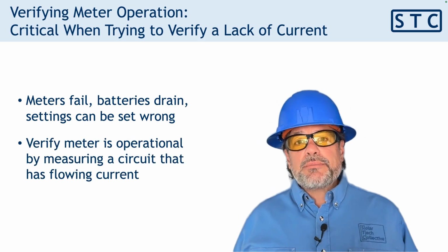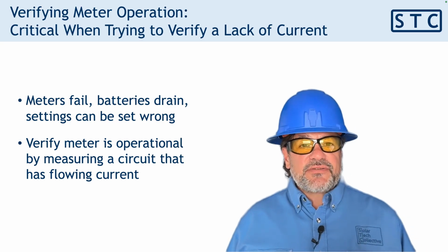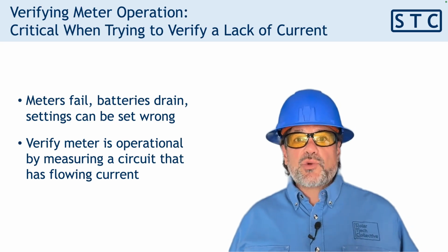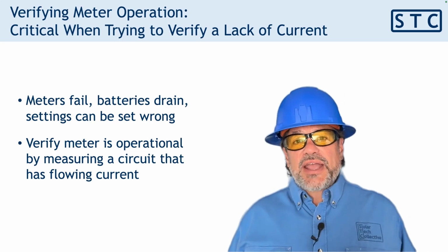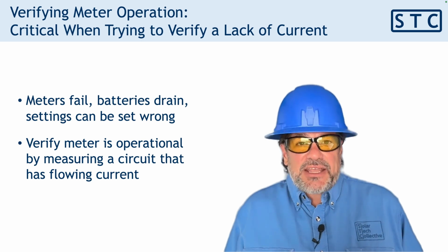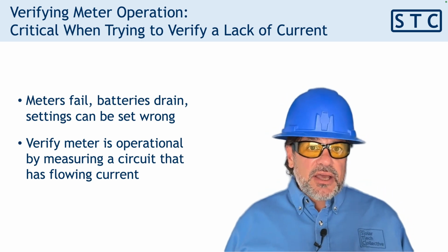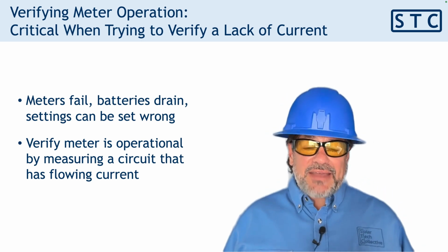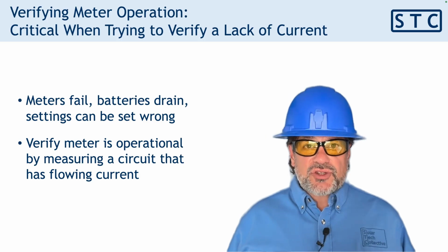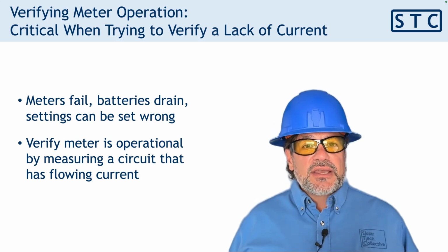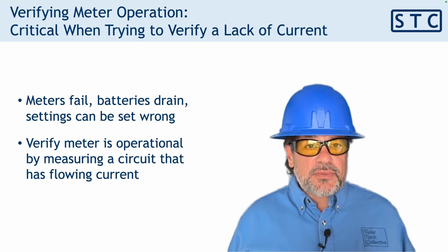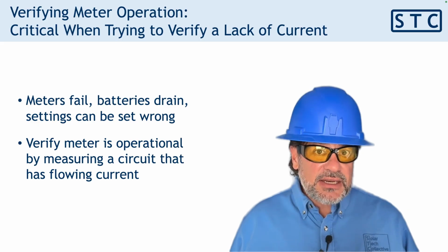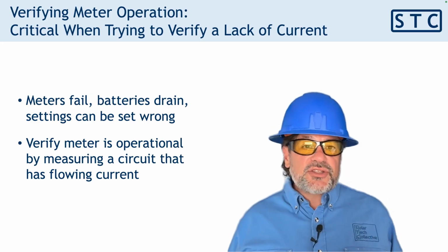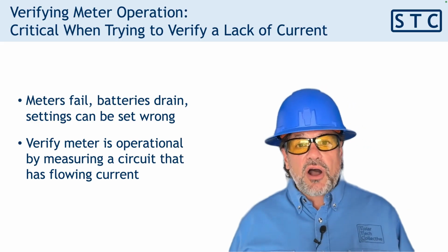So we want to go ahead and measure an operating circuit to verify that the meter can actually read current before we try and use it to make sure that there isn't any current. That could be testing the circuit before we shut it off and then retesting it when it is off to make sure there's no current. Or it could be testing a circuit on an adjacent system, maybe another inverter on site that's still operating if we've already turned our target circuit off.